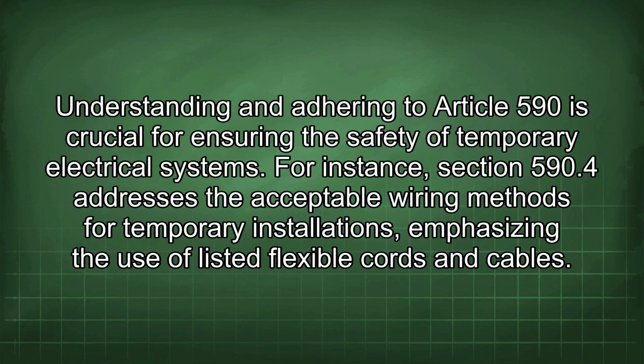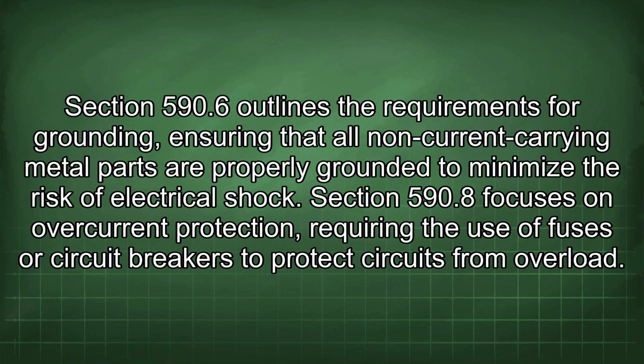For instance, Section 590.4 addresses the acceptable wiring methods for temporary installations, emphasizing the use of listed flexible cords and cables. Section 590.6 outlines the requirements for grounding, ensuring that all non-current carrying metal parts are properly grounded to minimize the risk of electrical shock. Section 590.8 focuses on overcurrent protection, requiring the use of fuses or circuit breakers to protect circuits from overload.